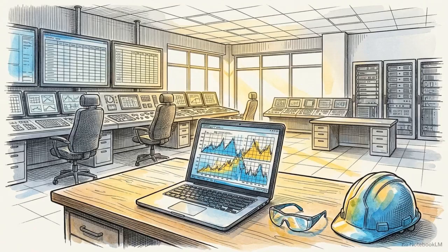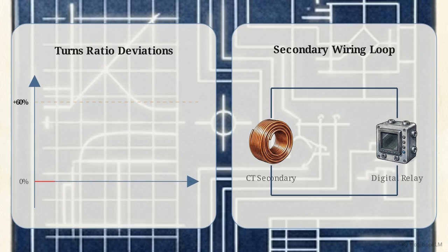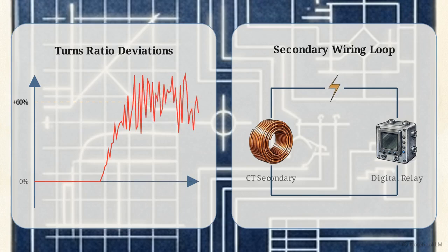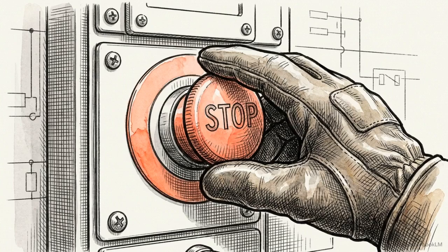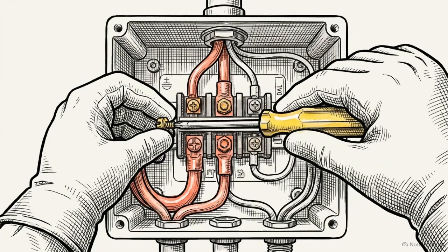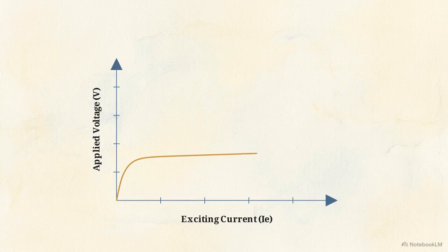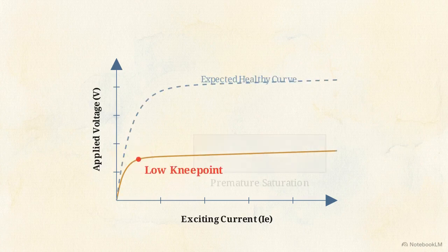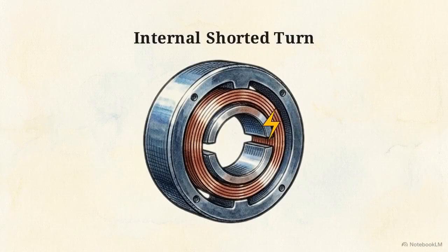With the primary tests concluded, the focus shifts to data analysis. Commissioning specialists must know how to interpret specific testing anomalies in the field. If the winding resistance values are abnormally high, or the turns ratio shows massive erratic deviations, it is the primary indicator of an unintended open circuit within the secondary wiring. The immediate resolution is to halt testing entirely and physically reinspect all shorting links, burden connections, and tap wiring for faults or loose landings. If the excitation curve returns an unexpectedly low knee point, the core is entering magnetic saturation far too early. This strongly suggests a shorted turn deep within the secondary coil, or that the technician is testing the wrong metering core.